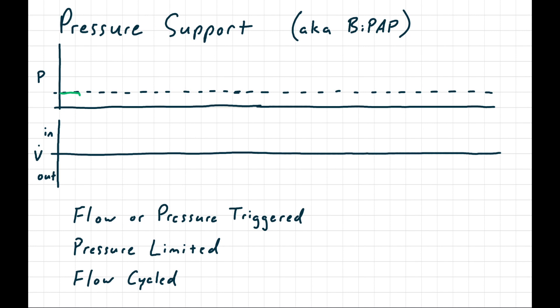Starting at end expiration with circuit pressure at PEEP, the patient initiates a breath — pressure decreases a little, flow increases a little. The ventilator recognizes this inspiratory effort, triggering inspiration. Circuit pressure increases to the preset inspiratory pressure, creating an initial increase in inspiratory flow which decreases as pulmonary pressure increases. In a patient who isn't paralyzed, they have some volitional control — they can lower their diaphragm and expand the ribcage to keep pulmonary pressure lower, or use respiratory musculature to increase it. So as circuit pressure stays constant at the set inspiratory pressure, flow will vary depending on what the patient is doing.